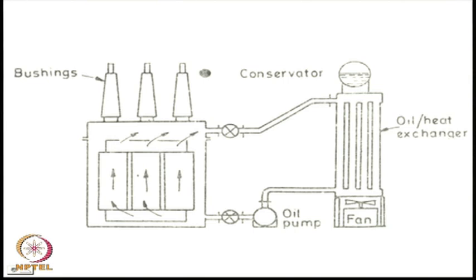The next important constructional feature of a transformer is its bushings. These are the bushings. These bushings are meant for making connection to the transformer from overhead lines. It has to be ensured that this transformer tank is normally earthed. So, when you are making a high voltage connection through the tank to the transformer winding, it has to be ensured that there is no flashover or short circuit or otherwise degradation of the insulation between the high voltage terminal and the earthed transformer tank. This is done through a special bushing.